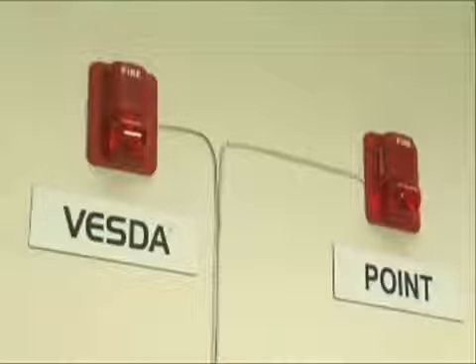Two types of smoke detectors compliant with international standards are put to the test. The following tests were conducted in a facility designed to emulate a telecom or data centre. Fire engineers, consultants, insurers, contractors, installers and end users were present. The tests will compare the time it takes for the two competing technologies to detect smoke and will show how factors such as air change rates and air dilution from air conditioning systems affect the time it takes for the fire to be detected. The first detector is an Xtralis VESDA air sampling or aspirating smoke detector.